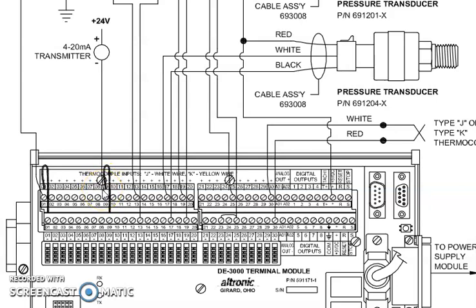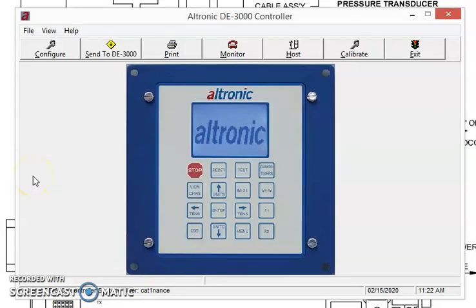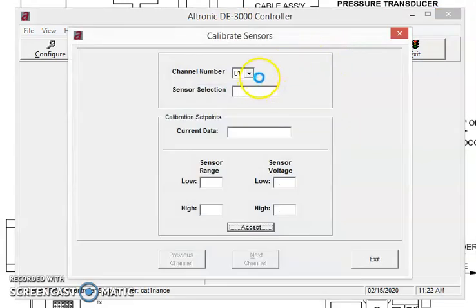And so in this case, what I've done is I've set up a simulation, and I have a 4 to 20 milliamp pressure transducer wired, and I have it tweaked just a little bit off, and we're going to try to get it back into calibration. So I'm going to connect my terminal program to my DE3000, and I'm going to click Calibrate, and we're going to focus in on channel 1. And here we can see that the sensor's been set up to be a 0 to 50. We can see that its current value is off just a little bit. We really want it to be reading 0. But here are my voltages that we're starting out with. 0.8 volts equals 0 psi. 4 volts equals 50 psi.